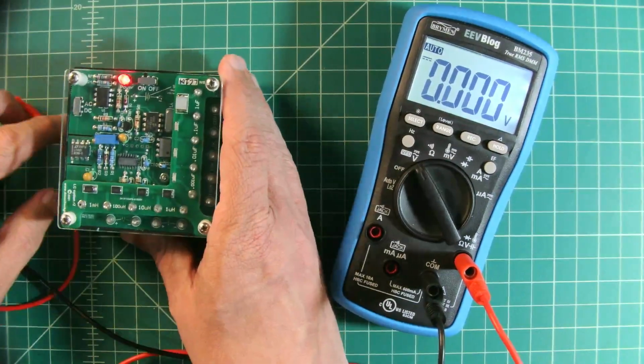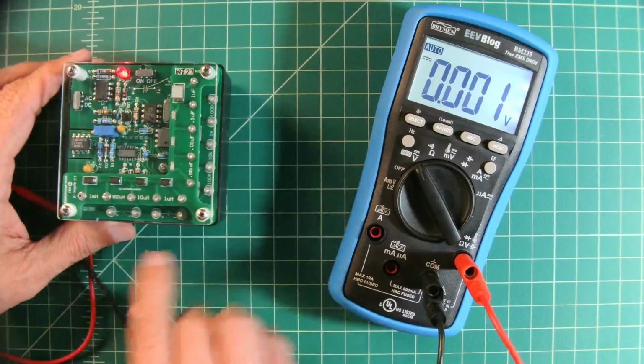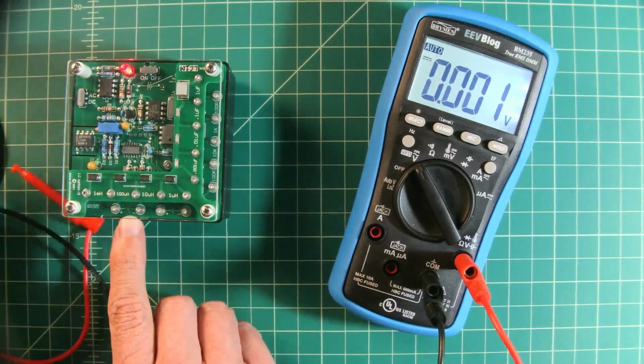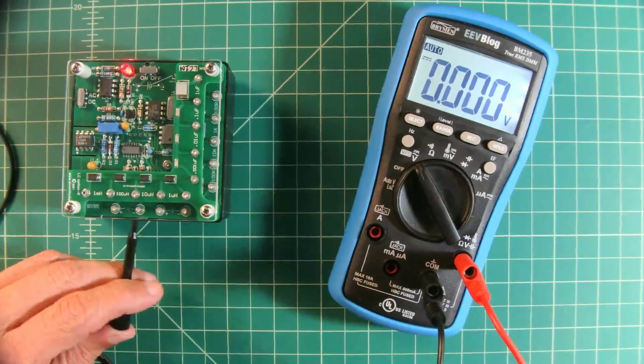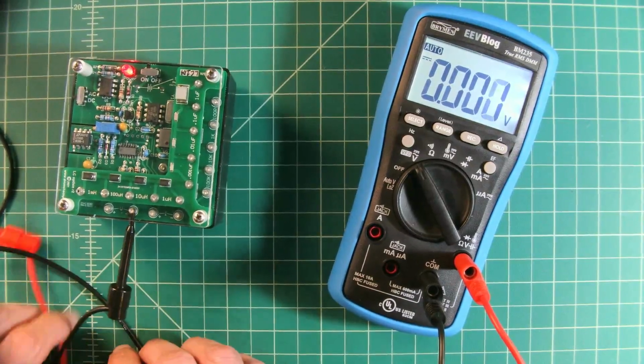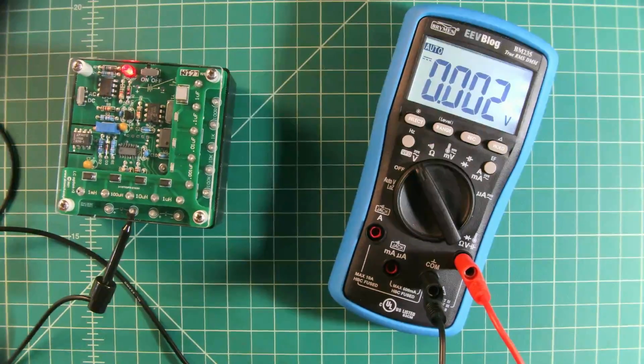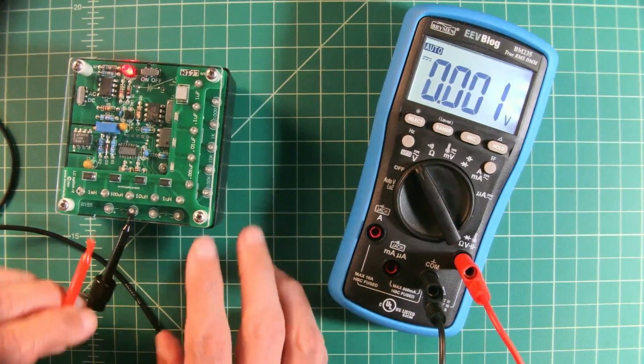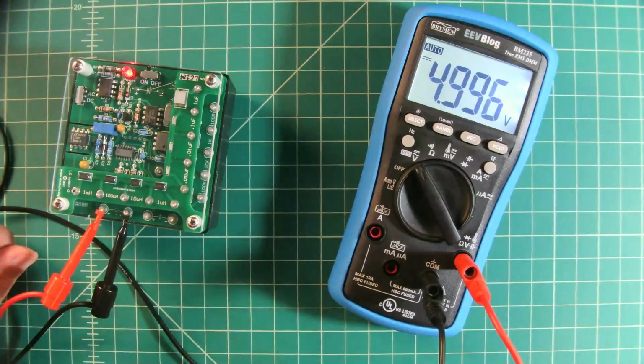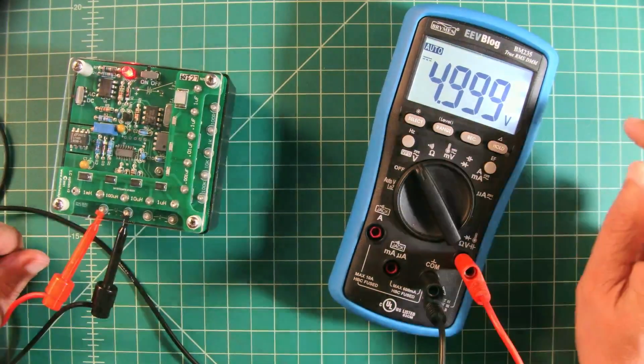I'm gonna switch it down to DC current. And then I'm gonna come here and you can see volts. I have a positive and negative terminal. I'm just gonna go ahead and connect this up to get us a reading. And according to my calibration sheet, I should get 5 volts DC, and it looks like we have 4.99.